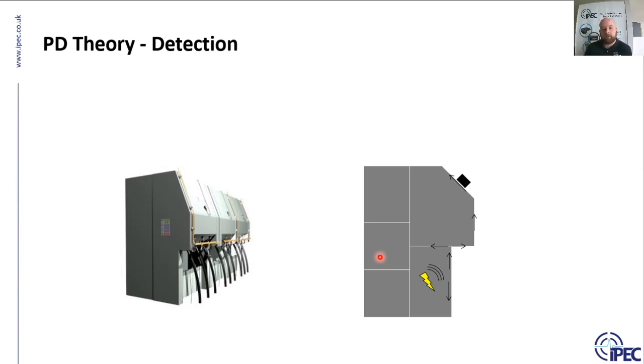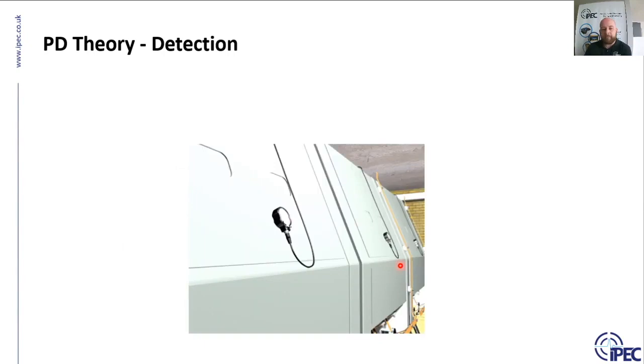across the switchgear surface. So here's another one of my fantastic animations. Out from the gaps in the panel and being induced across the surface of the TEV. Out from the gap and induced across the surface of the TEV. Now, it must be noted that PD, again, will travel in all directions away. It'll travel across the surface, across many panels. And so just because you're detecting the PD on one single panel does not necessarily mean that's the source of the PD. And I'll comment a little bit later on how we would attempt to locate those things.